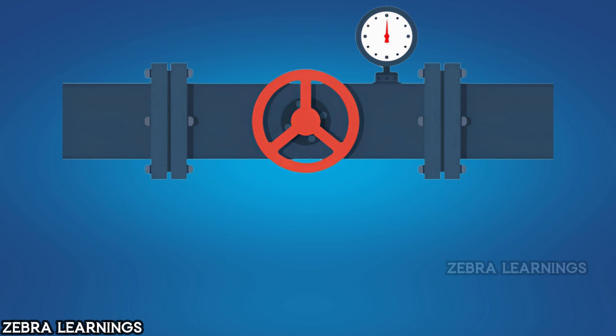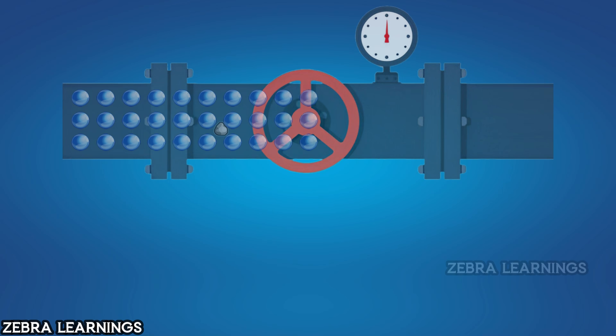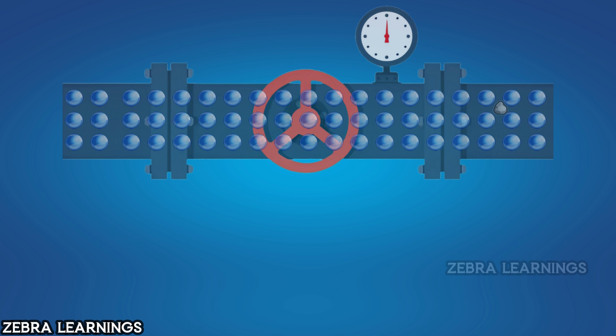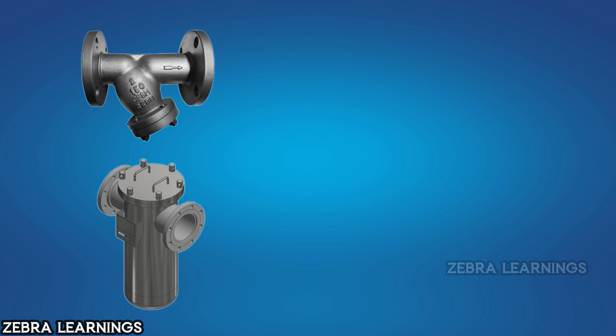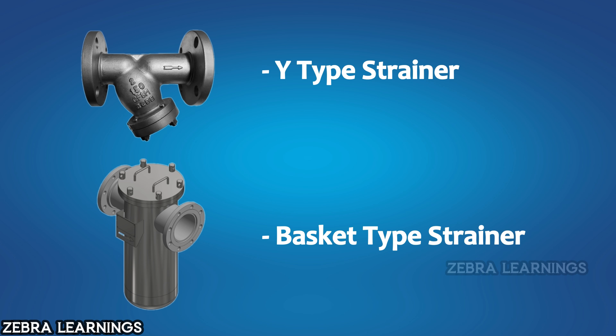In HVAC systems, there is often a lot of debris in the water flowing through the pipelines. We use strainers to filter out this debris. In HVAC, we use two important types of strainers: the Y-type strainer and the basket-type strainer.